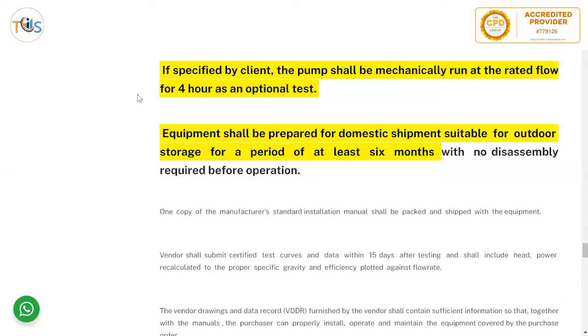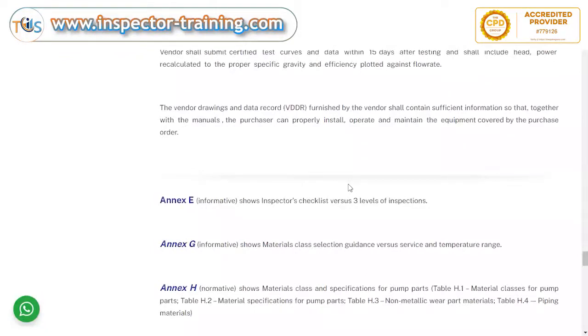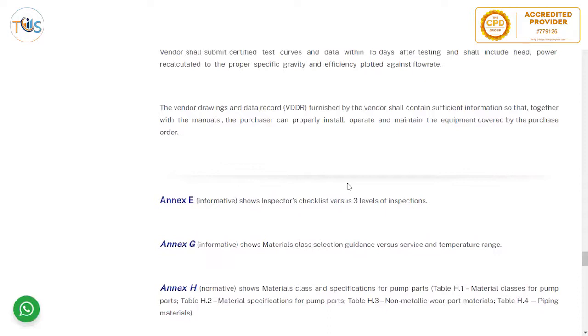Equipment shall be prepared for domestic shipment suitable for outdoor storage for a period of at least six months with no disassembly required before operation. One copy of manufacturer's certified test curves shall be provided within 15 days after testing, and shall include head, power recalculated to the proper specific gravity, and efficiency plotted against flow rate. Since tests are done with water (specific gravity of 1), the results must be adjusted to the actual fluid's specific gravity for actual operating conditions.